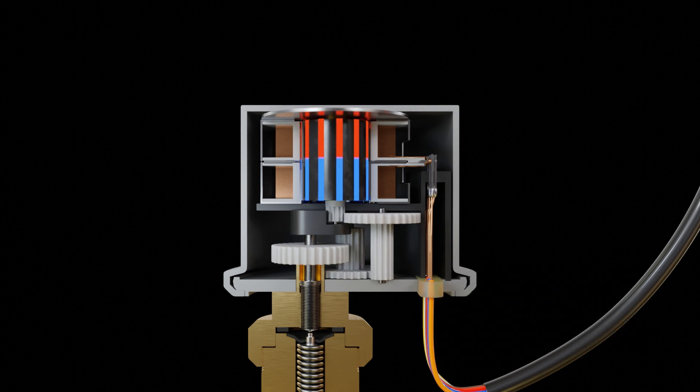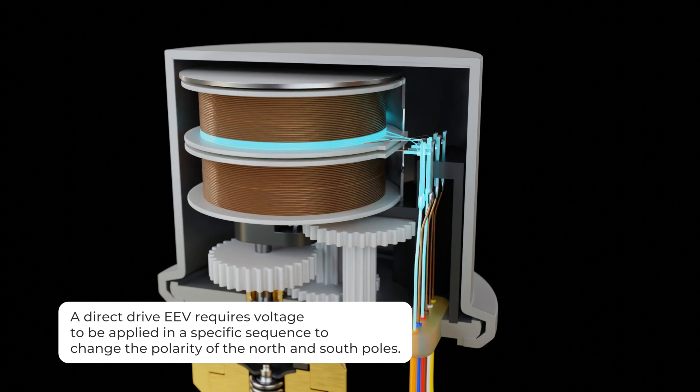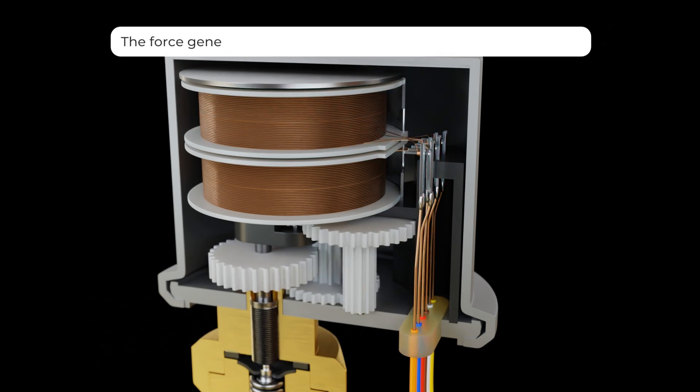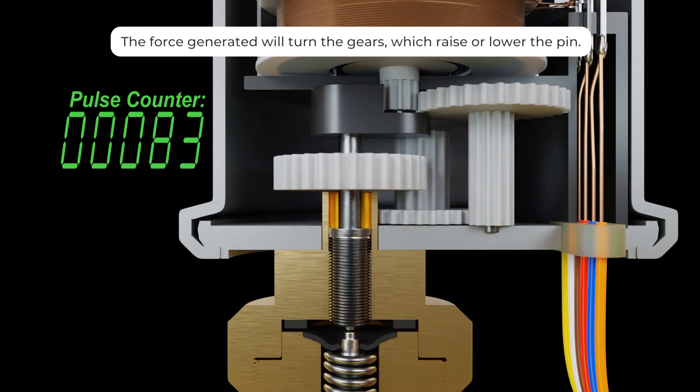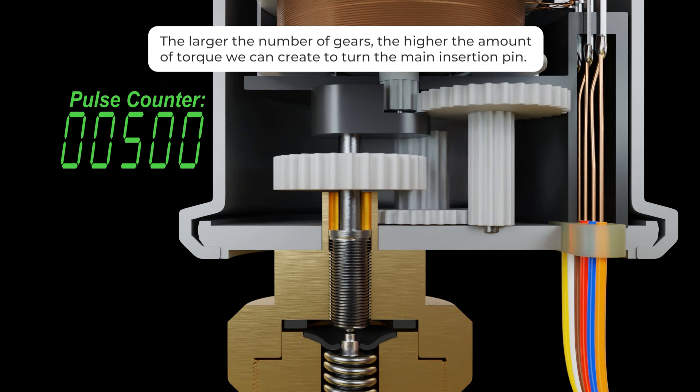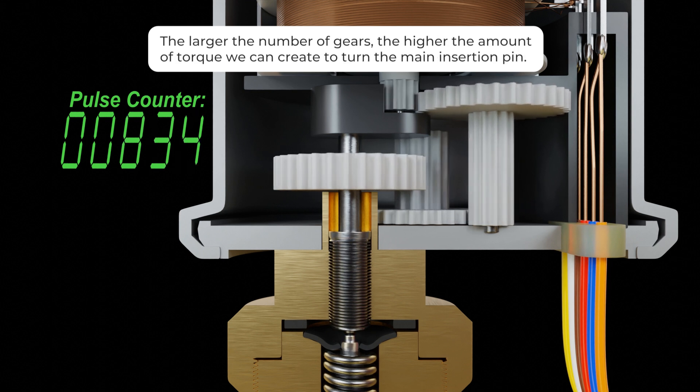As with the EEV with an indirect motor, a direct drive requires voltage to be applied in a specific sequence to change the polarity of the north and south poles. The force generated will turn the gears which raise and lower the pin. The larger the number of gears the higher the amount of torque we can create to turn the main insertion pin.